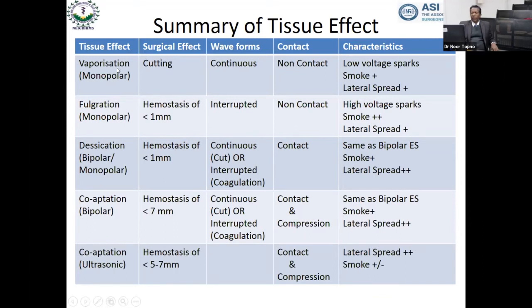This is when temperature goes beyond 100, you get the vaporization effect and therefore the cutting. And fulguration is basically a monopolar function. Most importantly, it is a non-contact process, just like vaporization and cutting. The electrode need not touch the body surface which you want to cut. But if you keep it just a few millimeters away from it, the current actually jumps across, and that is how the cutting effect or the coagulation effect in fulguration happens.